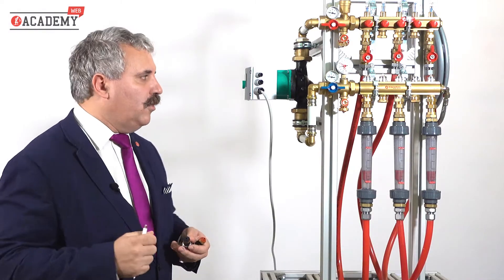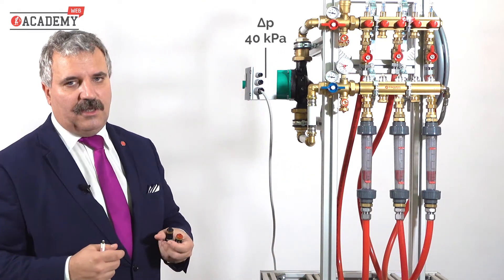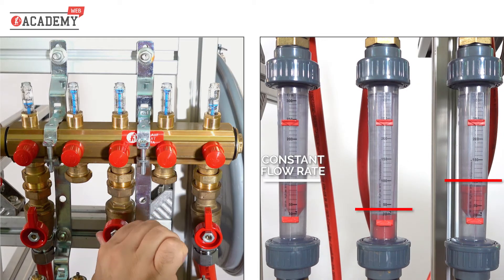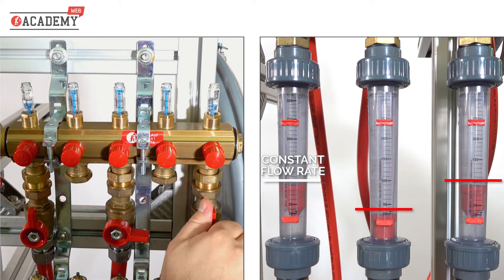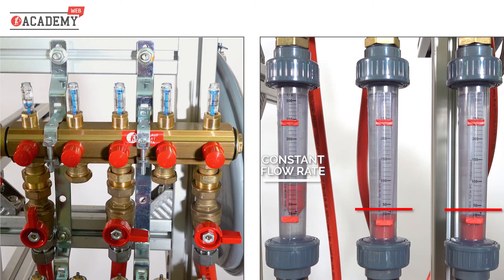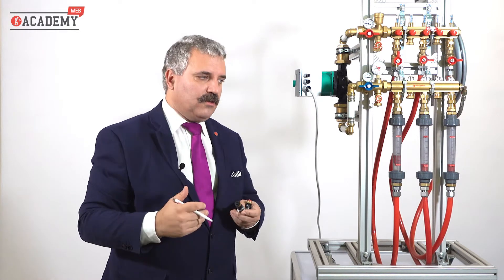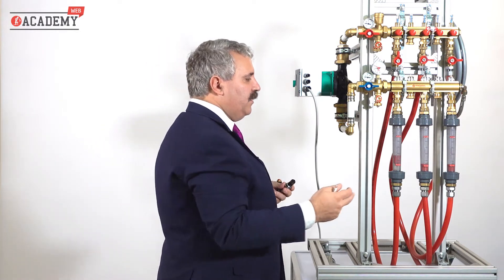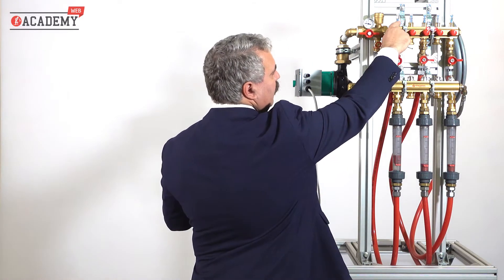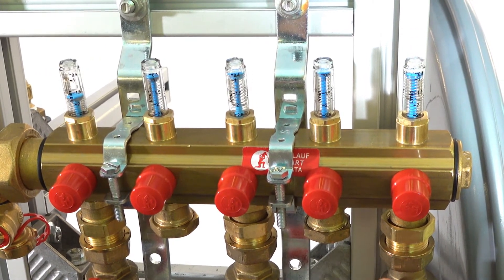Let's take a look at the actual operations. To make it easier, we balance the same flow rate for all loops and see what happens when closing some loops. As you can see, the flow rate in the loops we left open doesn't change, remaining constant and stable. That's the result of the function of this type of cartridges. Here we have the flowmeters to better show the flow rates, and of course the flow meters on the manifold perfectly show the same result on the actual flow rates.